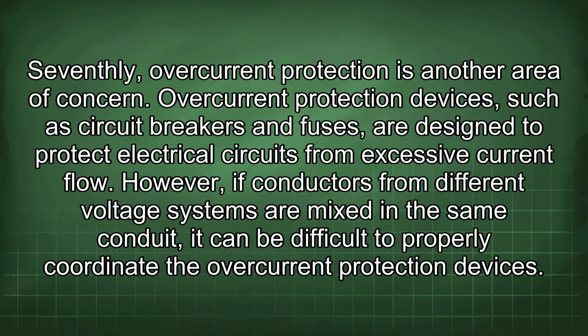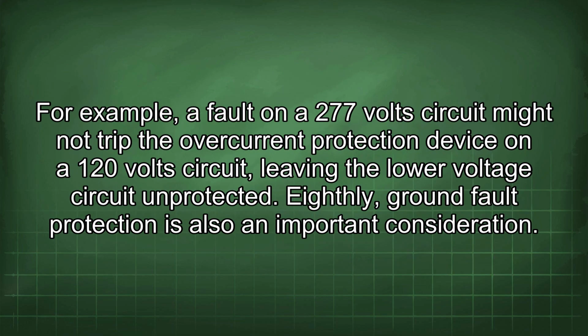Seventhly, overcurrent protection is another area of concern. Overcurrent protection devices, such as circuit breakers and fuses, are designed to protect electrical circuits from excessive current flow. However, if conductors from different voltage systems are mixed in the same conduit, it can be difficult to properly coordinate the overcurrent protection devices. For example, a fault on a 277-volt circuit might not trip the overcurrent protection device on a 120-volt circuit, leaving the lower voltage circuit unprotected.